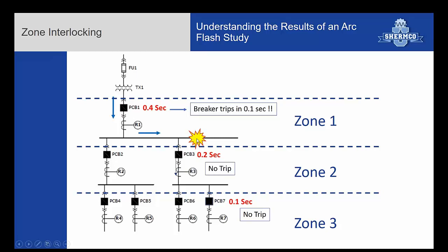So when this fault occurs in the zone, since neither one of these would be sending this signal back to the main, it would trip instead of its settings at 0.4 seconds or whatever it's at. It would trip almost instantaneously, which would make the arc flash much less in this area. These work pretty well, especially in newer switchgear. This zone interlocking is typically a 24 volt signal that goes from one trip unit to the other. 24 volts is not a lot to work with. If you have bad connections or others, you could have some reliability issues. But typically in newer switchgear, that's pretty well thought out.